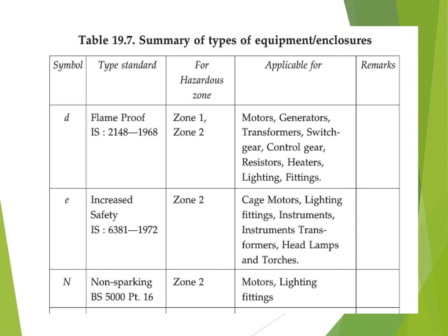Now we can see a summary of the types of equipment we have discussed. Flame proof, which comes under type D, is used for hazardous zone 1 and zone 2. Generally it is applicable to motors, generators, transformers and control gear. And type E, increased safety, IS code is IS 6381-1972. It is used for hazardous zone 2, applicable to cage motors, squirrel cage motors, lighting fittings, instruments, headlamps, torches, etc. And type N, non-sparking, zone 2, is applicable to motors and lighting fittings.